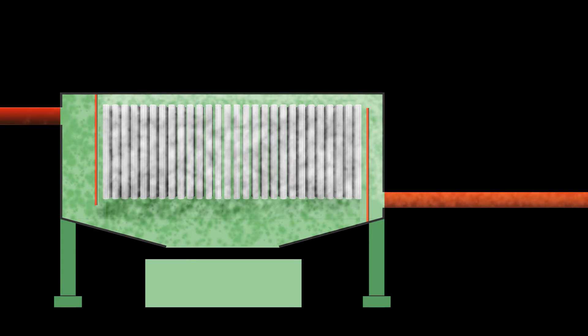When fabric filters are used, the bags are supported by internal wire cages. The PulseJet cleaning cycle is controlled by a solid state timer which sequentially pilots pulses of compressed air in the reverse direction of filtering into blow pipes mounted above each row of filters.